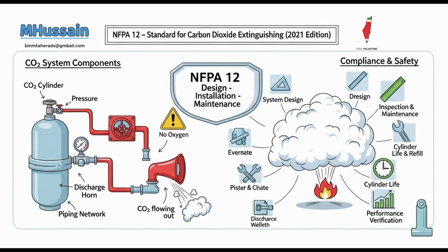And what about safety around electrical equipment? While CO2 is non-conductive, what are the specific rules regarding electrical clearances for the system components themselves? Indeed, while CO2 itself won't conduct electricity, all system components, the piping, nozzles, detection devices, and wiring must maintain specific minimum clearances from live electrical parts. Keep the pipes away from the live wires. Essentially, yes. The standard provides a detailed table, Table 4.3.4.1, which outlines these requirements. For voltages up to 161 kV, these clearances are derived from NFPA 70, the National Electrical Code, the NEC, which defines safe distances to prevent arcing.